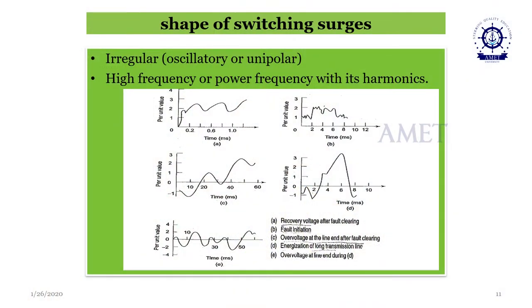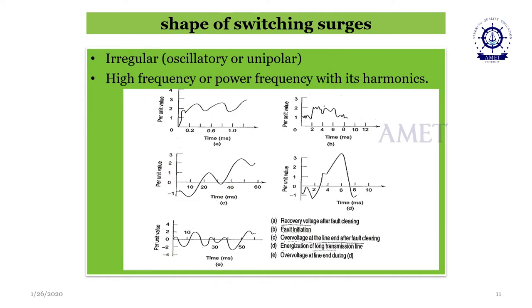The waveform has a very high peak, a steep rise, and a slower diminishing in the value, and then over voltage at line end. So the final waveform, the E waveform, represents the over voltage at the line end, that is the end of the transmission system, which we call the termination end, where we basically connect the load. Out of all these five, we can see different patterns. It is not a common pattern, it is shapeless, and the pattern keeps varying from action to action, device to device, and process to process.